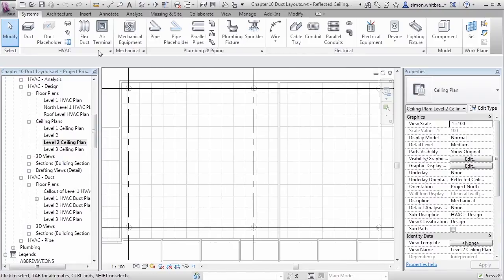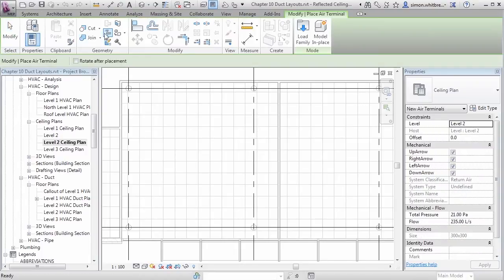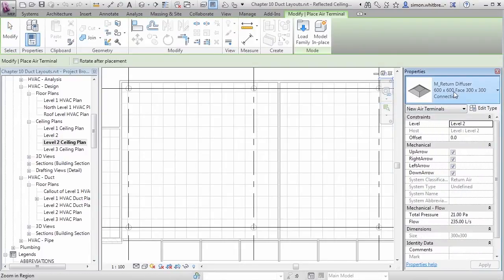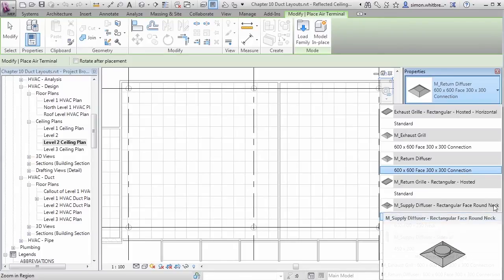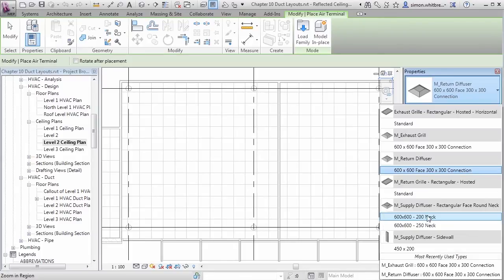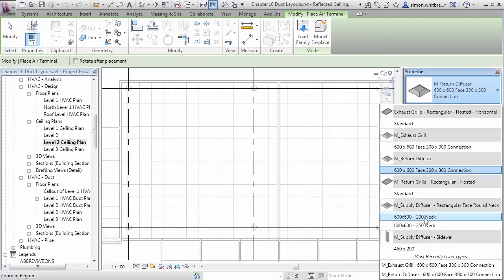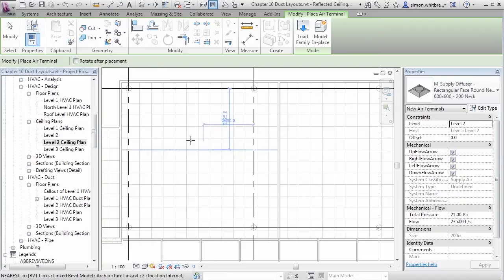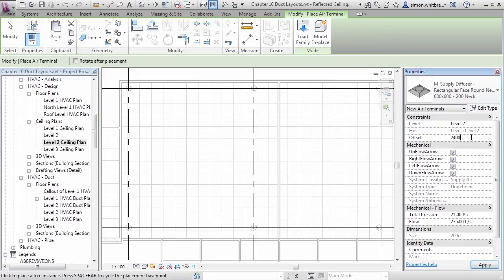In this layout go to your Systems tab and click on Air Terminal. We're going to use the Supply Diffuser with a rectangular face and a round neck. The type we're selecting is the 600 by 600 with a 200 neck. As this is an unhosted family, I need to start by setting my ceiling height.